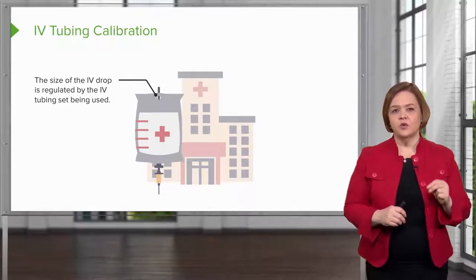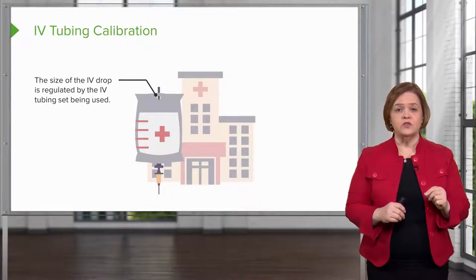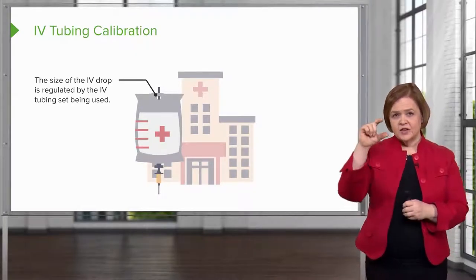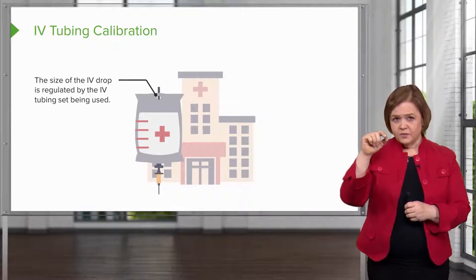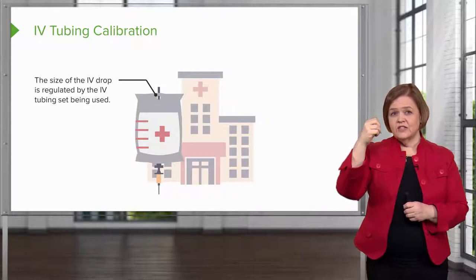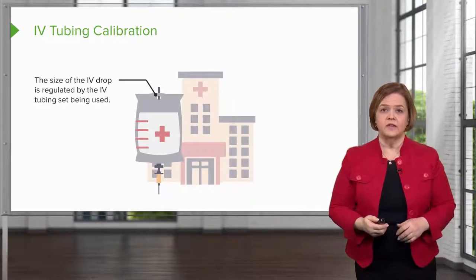The size of the IV drop is regulated by the IV tubing set being used. That means that in that drip chamber, when you see those drops come down, the volume — how much fluid is in that drop, the size of that drop — is regulated by the tubing set that you're using.